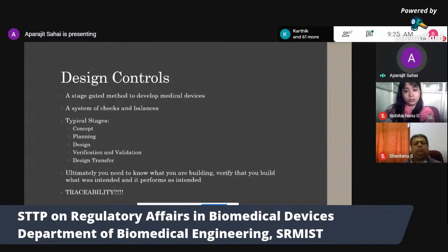And then what that gives you is something called a marketing requirement specification document. So essentially they're rough requirements, for example, the device should be light, the device should be easy to use. Those requirements are not specific. Like I said, easy to use, they should be able to detect blood flow in the carotid artery. That's a very general requirement. In a later phase, we'll talk about how those convert into engineering requirements, but we'll come to that.